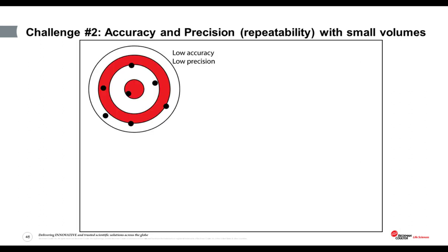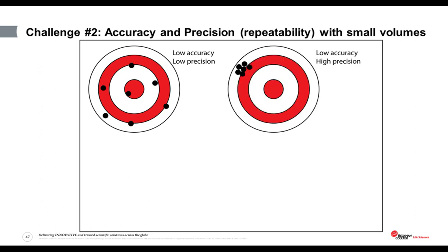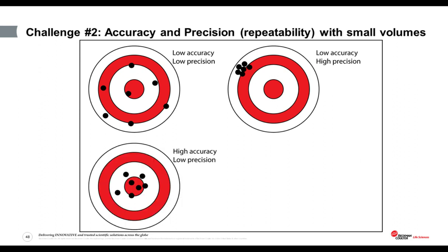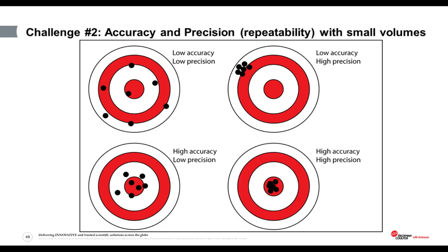The second challenge is whether the counter can achieve accuracy and precision or repeatability with sample volumes as small as 0.2 milliliters. So I'm going to use the target here to explain just what I mean. In the first picture, subsequent shots at the central bullseye result in hits all over the target. And this can be described as having neither accuracy nor precision. However, in the second picture, all the shots are bunched together tightly, but they're not hitting the central bullseye. Now, this is good precision, but poor accuracy. In the third picture here, the shots are all close to the bullseye, with 1 or 2 actually hitting it, but the shots are still scattered. And this can be described as having good accuracy, but poor precision or repeatability. And finally, in the last picture, this is what we want, where the shots have all landed in the bullseye, repeatedly demonstrating both good accuracy and precision. And this is the performance we need from our light obscuration particle counter.